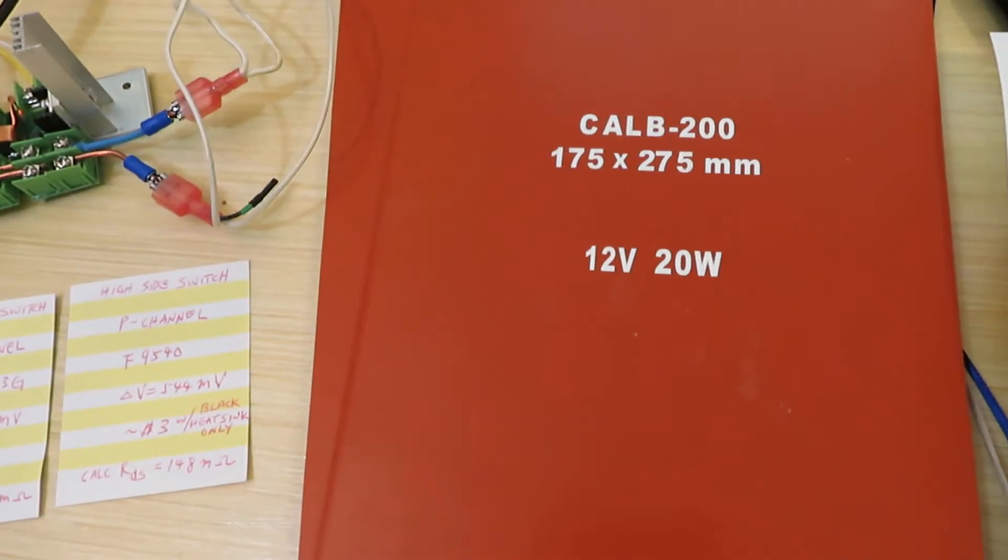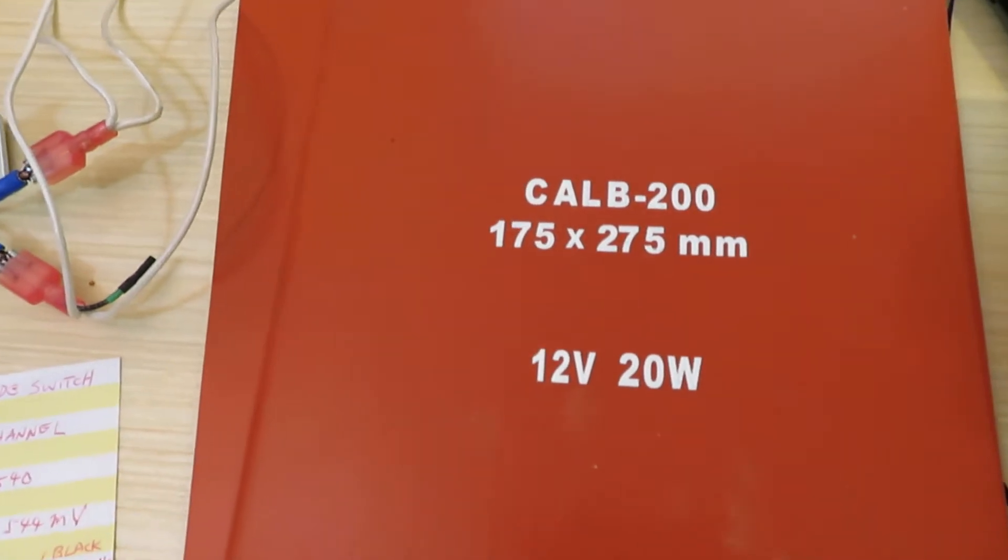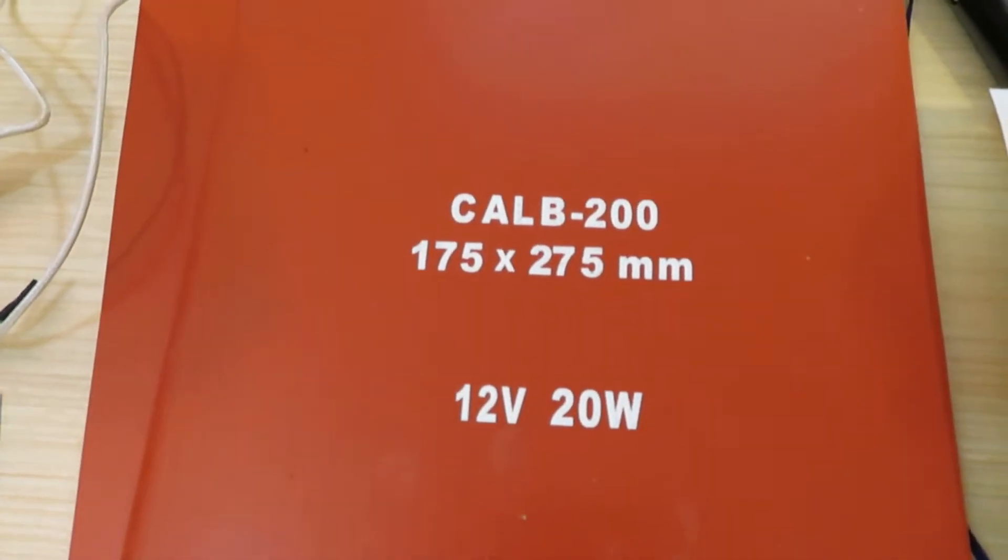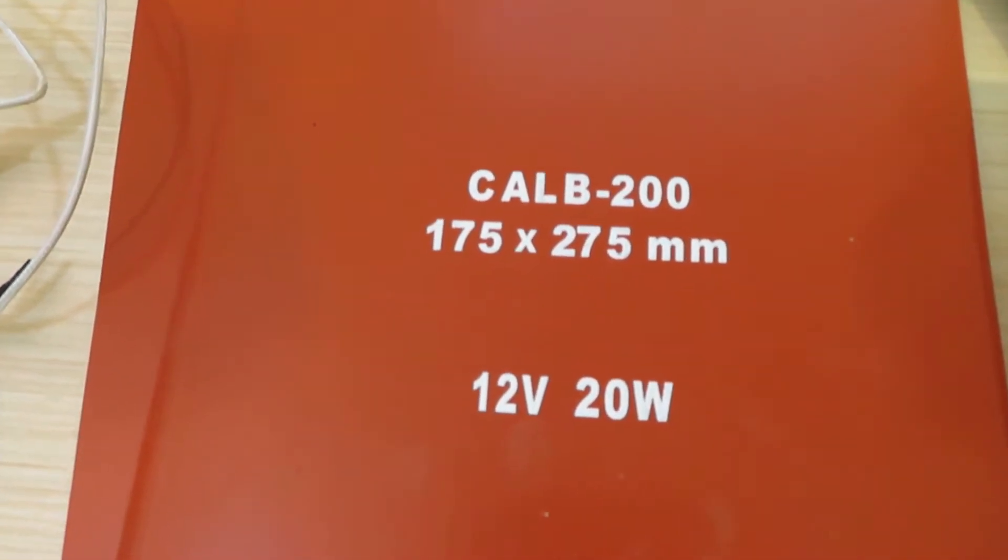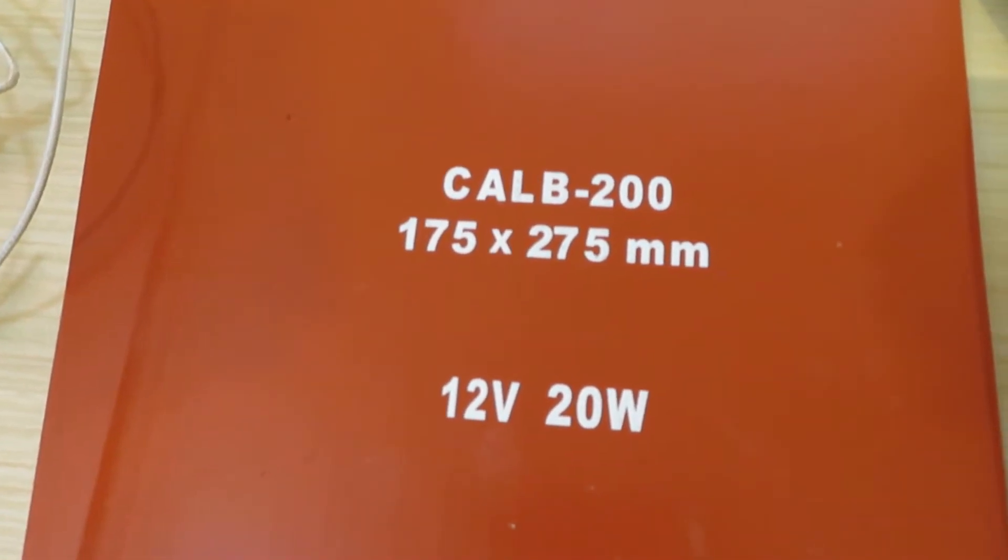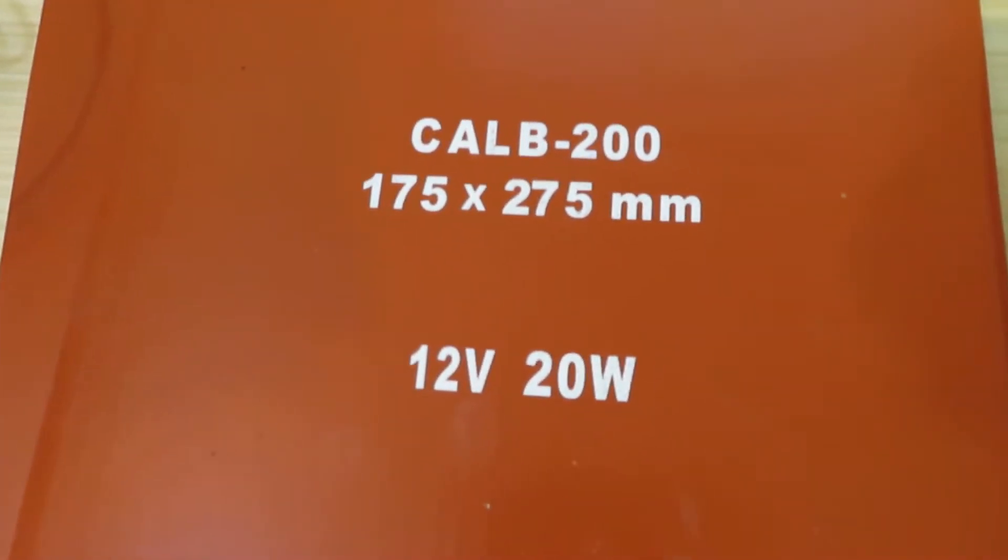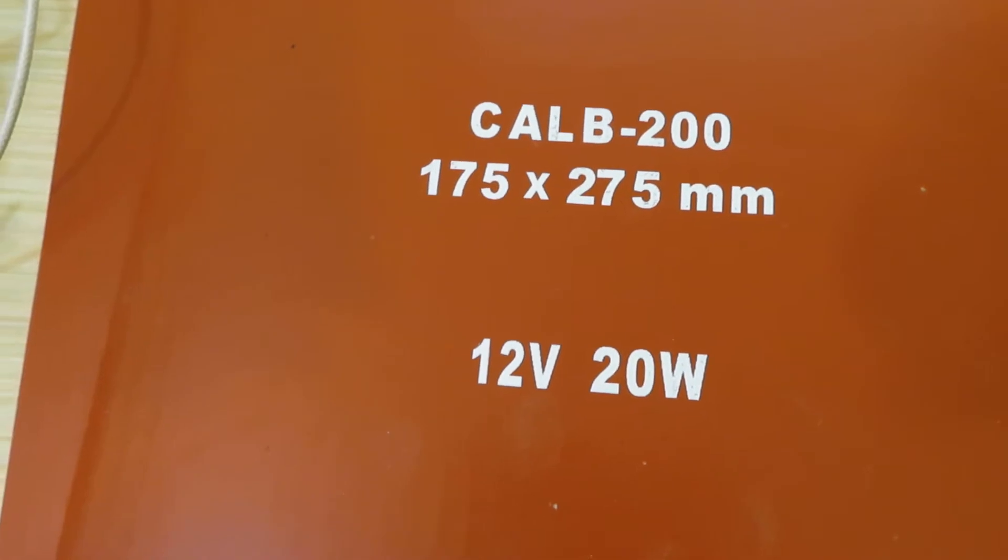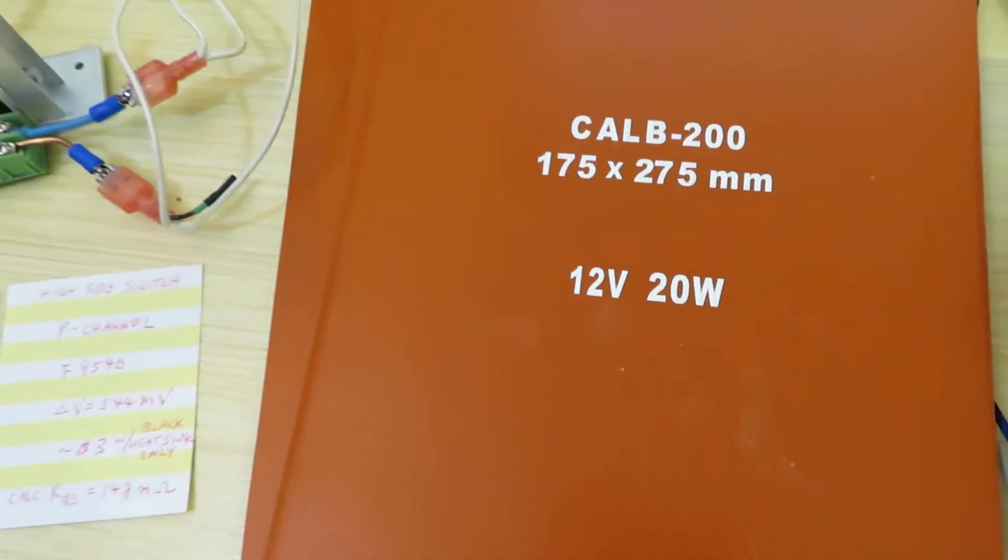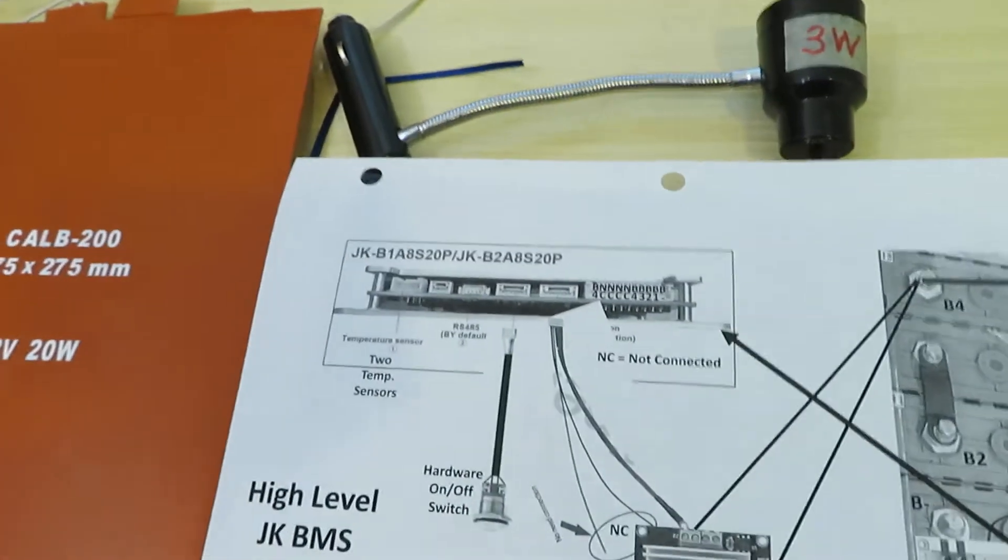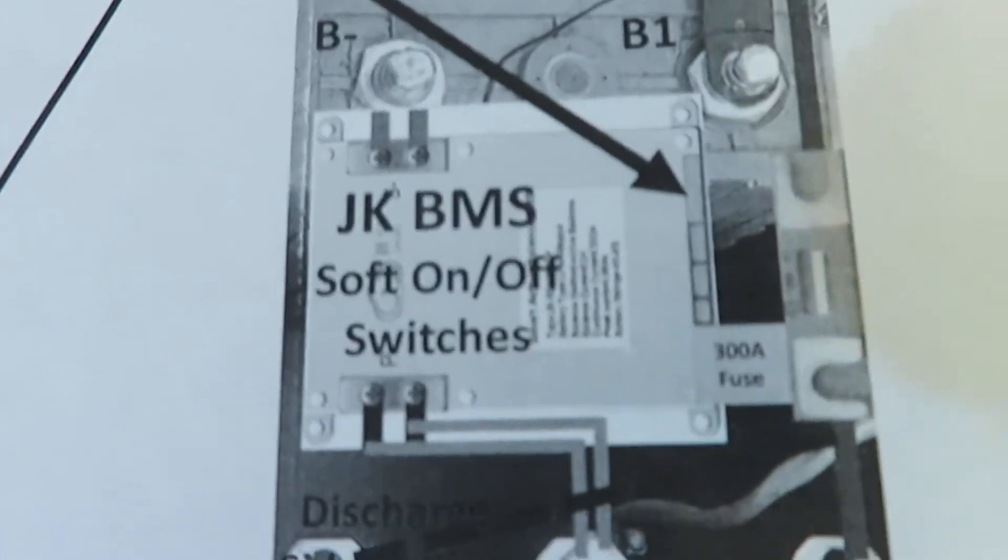The heating pad is actually two of them for the EcoTrack battery, 20 watt each, so a total of 40 watt. And because the JK BMS heating pad driver port is only good for 3 amps, it cannot drive the heating pad directly.